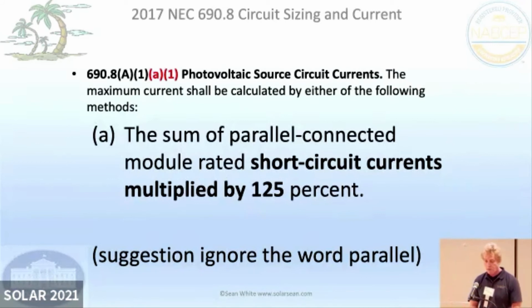For current, we're very conservative, and we take the short circuit current, which hopefully you never have a short. That's just like shorting out. And we multiply it by 1.25 to get our current that we work with. And then we multiply it by another 1.25 that we do for everything else, because it's something that goes for 3 hours or more. It's called continuous current. There's these two different 1.25s for a PV source circuit that you end up using. And then if it's hot, so you're in the sunlight, then you might have other correction factors. So it just gets kind of complicated with your PV source circuits.